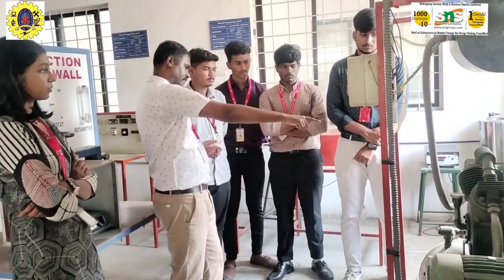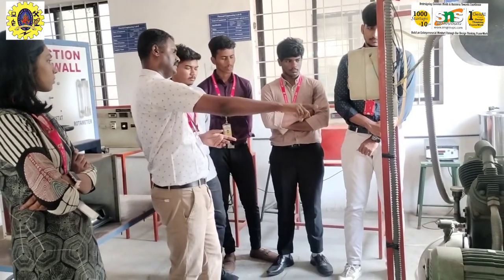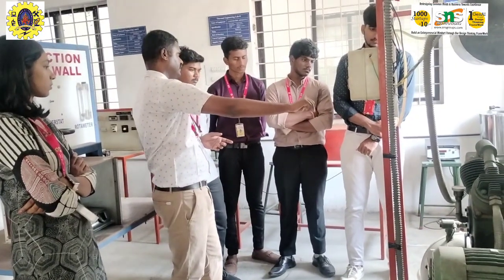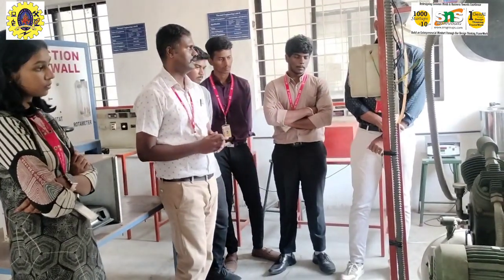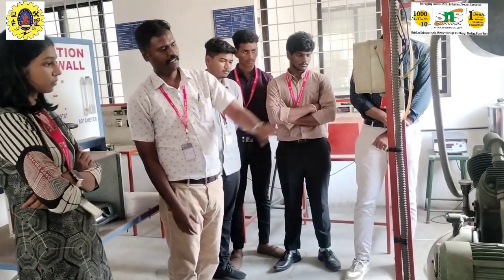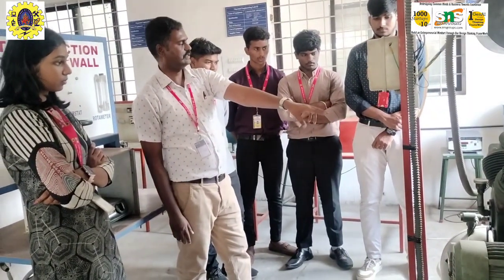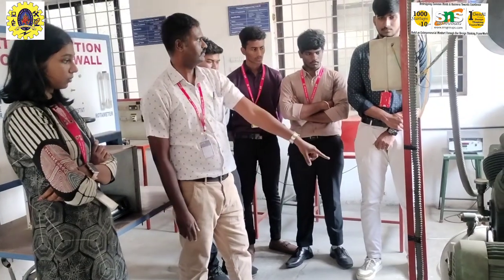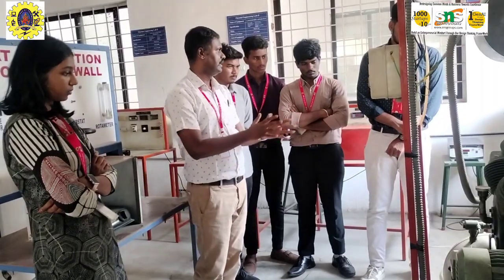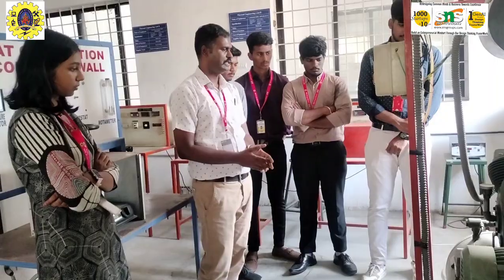Once the air is compressed in the piston, the outlet valve opens and it delivers the air to the intercooler. In between, the center pipe provided with fins is called the intercooler. The intercooler is used to cool the compressed air. Then it is sent into the second stage compression. After compression in the second stage, it is sent to the reservoir, where we can store the air. The reservoir is provided with a pressure gauge, so we can measure the pressure of the stored air.